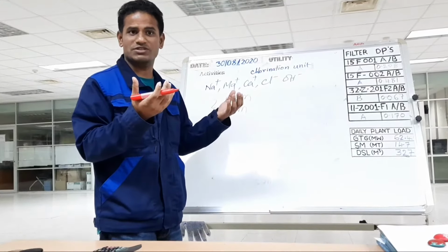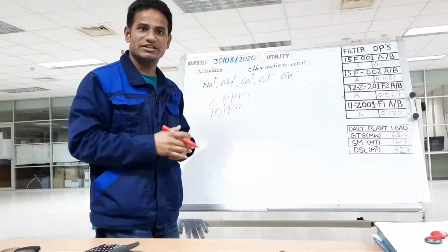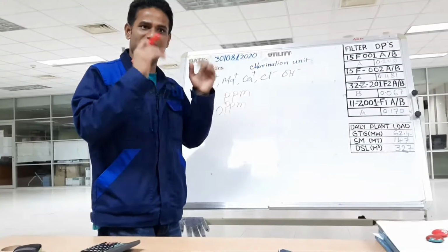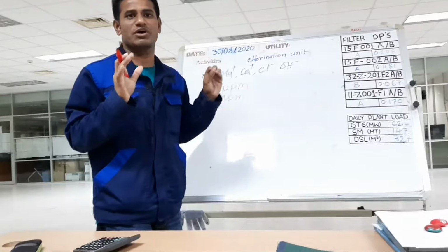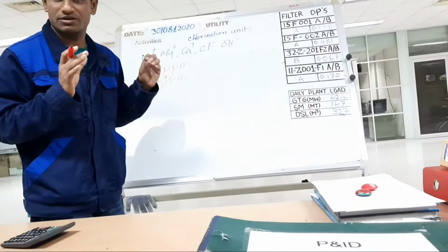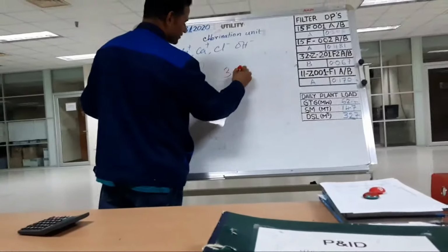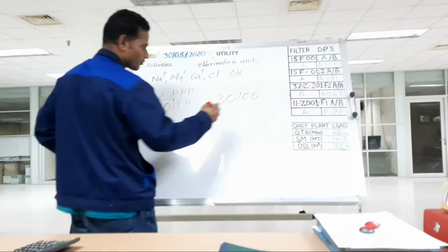270 kg for how much flow? Around 1,35,000. If 1,35,000 flow, that time 270 kg chlorine is required. Now only 4 pumps are running. One pump capacity how much? Seawater pump 30,000, maximum this. Normal one pump capacity 30,100. So multiply for 4 pumps.